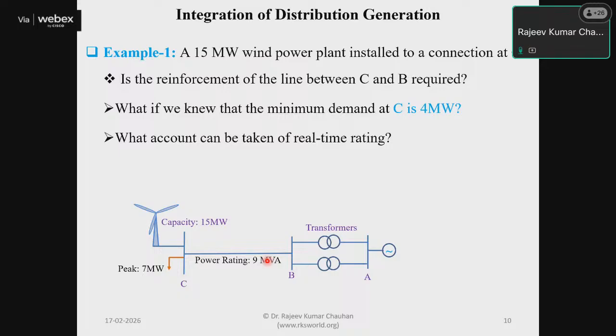For example, consider a 15 megawatt wind power plant installed at connection C, since it can be installed at different locations. If reinforcement of the line between B and C is required, what if we knew that the minimum demand at C is 4 megawatts instead of 7 megawatts? If this plant drops down to 4 megawatts, who will take care of it? It means 11 megawatts will be surplus generation, and the rating of this line is less than that, so we have to curtail the power generation from the wind power plant.